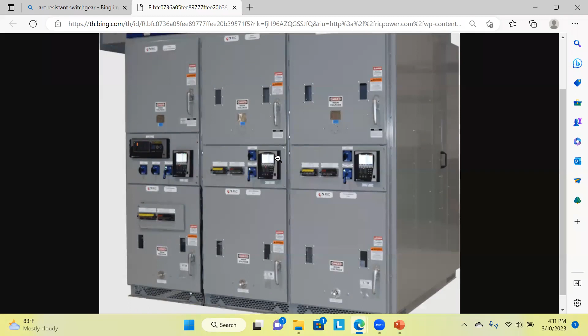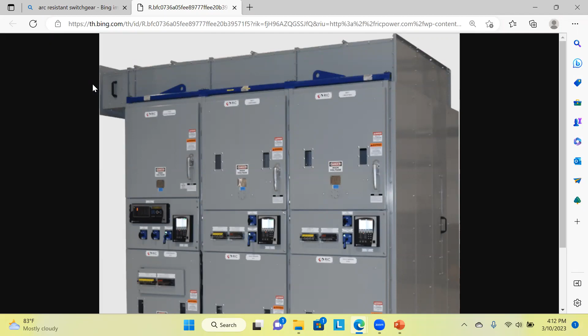But with this arc resistance switchgear, which is a bit costly compared to the metal clad switchgear, due to any internal arc or malfunction during operation, the energy generated during an arcing event will not come towards the person. It will be directed upward through this chimney into the air. So this arc resistance switchgear redirects the energy released during an arcing event or fault condition.